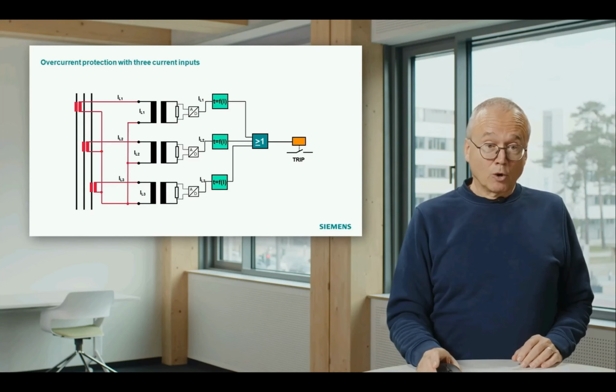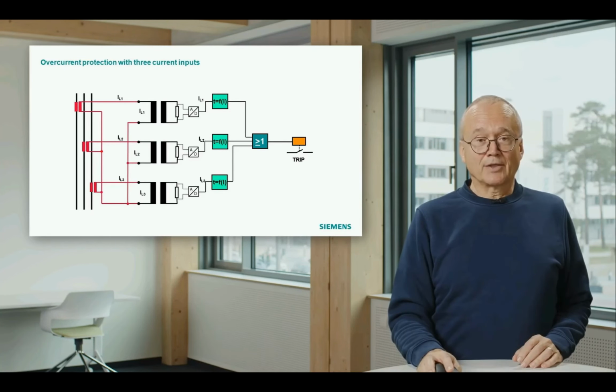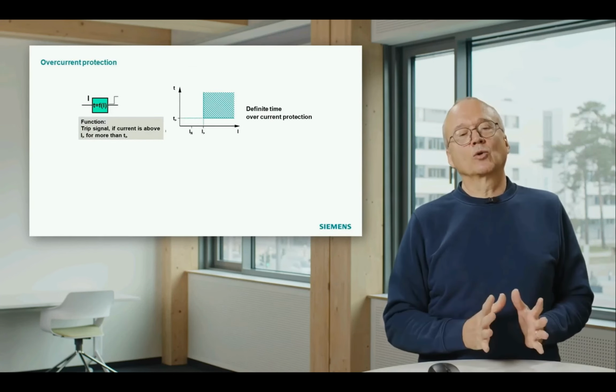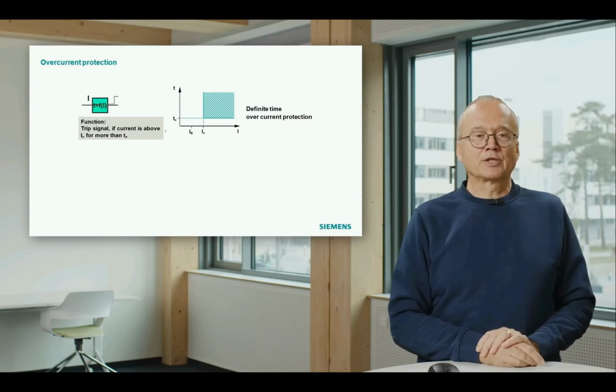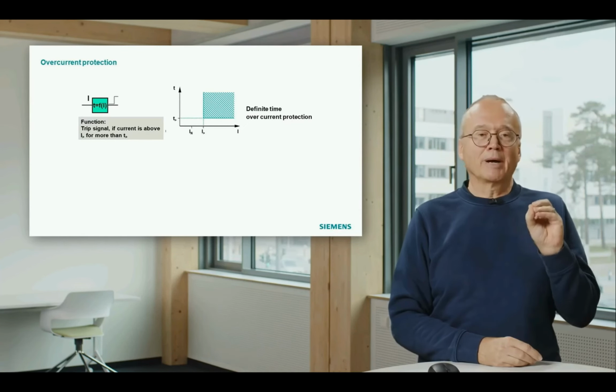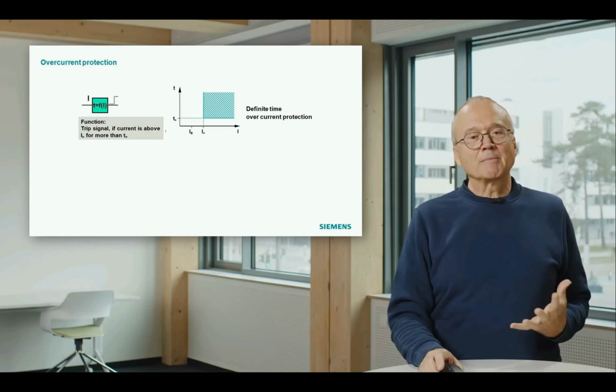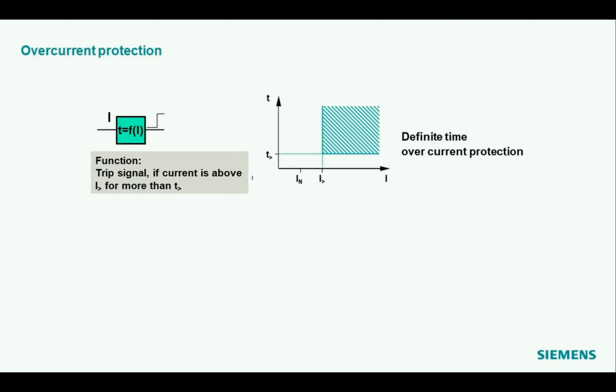Now let's look a little bit more into these blue boxes. What is inside there? That is shown on the next slide. As I already mentioned, we have 2 types of overcurrent protection, and they can be distinguished by looking into these boxes. That means these boxes have a different characteristic, that means a delay time depending on the current they detect. This characteristic is normally plotted in a diagram like the one you see here on the right side. The horizontal axis is the current we measure, and the vertical axis is the delay time. And what you see here is a certain range of current from 0 to the setting value. This is the setting value.